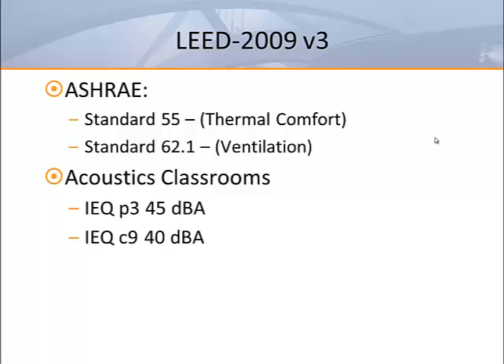LEED certification for schools requires IEQ Prerequisite 1 to meet ASHRAE Standard 62.1, Sections 4 through 7, which include IAQ ventilation rates in Section 6. IEQ Prerequisite 3 requires a maximum background noise level for HVAC systems in classrooms of 45 dBA. IEQ Credit 2 gives an extra point for increasing the ventilation air to the space by 30% over the Section 6 requirements.